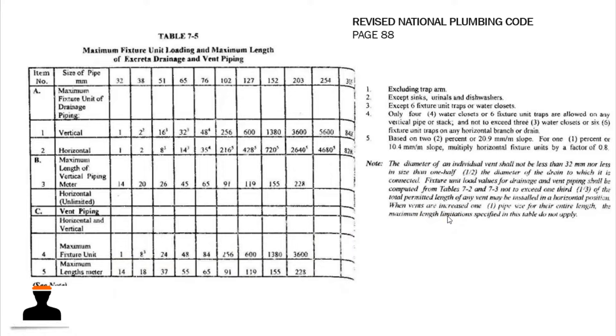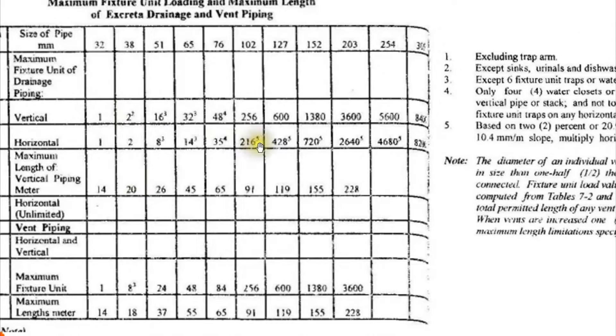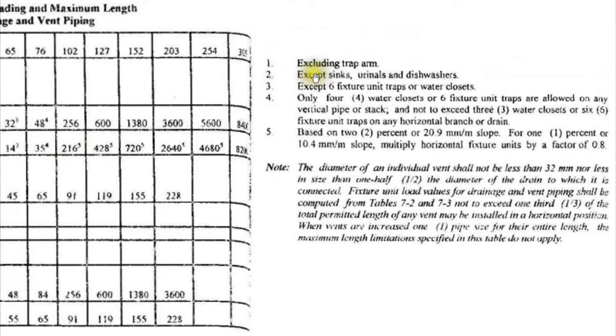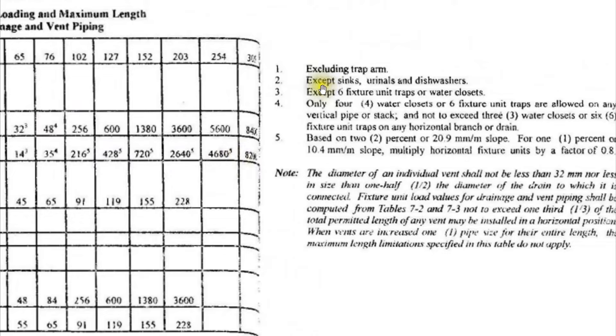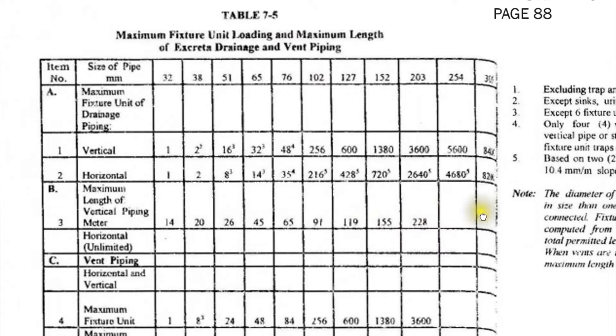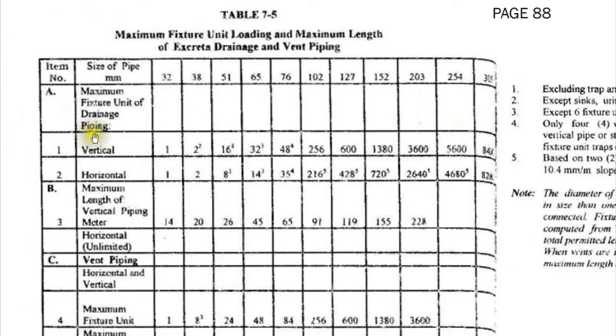When you compute the total drainage fixture unit, trace where it falls in the table — just like what we did in designing the water supply pipe. Now if your fixture unit falls under a value with a superscript, check the notes. For superscript 2: you can choose that value, however you should not consider sink, urinals, and dishwashers. If those three fixtures are connected to your vertical pipe, move to the next higher value, which is 16.